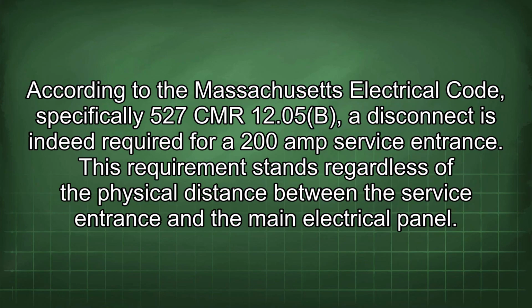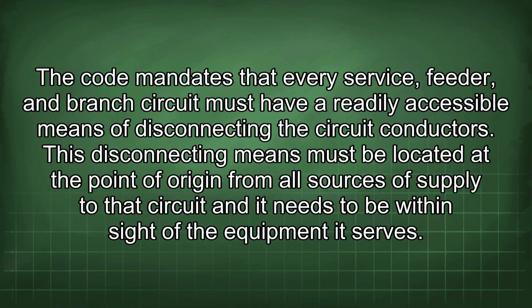According to the Massachusetts Electrical Code, specifically 527 CMR 12.05(B), a disconnect is indeed required for 200 amp service entrance. This requirement stands regardless of the physical distance between the service entrance and the main electrical panel. The code mandates that every service, feeder, and branch circuit must have a readily accessible means of disconnecting the circuit conductors. This disconnecting means must be located at the point of origin from all sources of supply to that circuit, and it needs to be within sight of the equipment it serves.